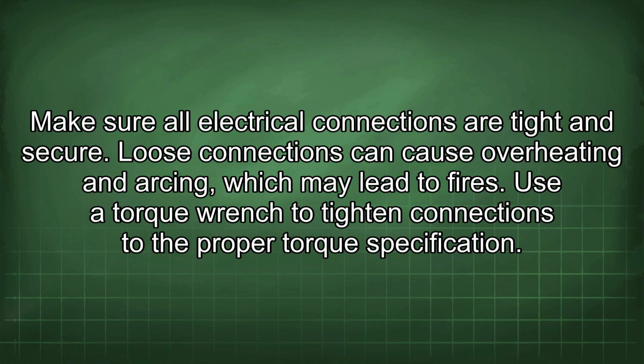Make sure all electrical connections are tight and secure. Loose connections can cause overheating and arcing, which may lead to fires. Use a torque wrench to tighten connections to the proper torque specification.